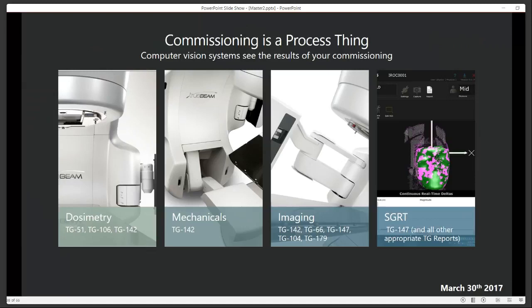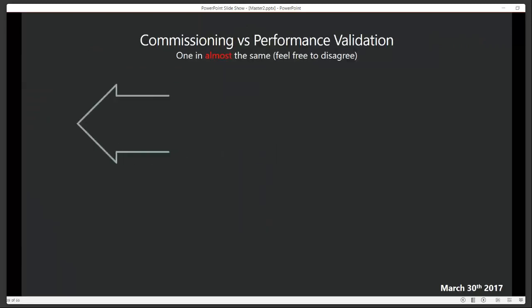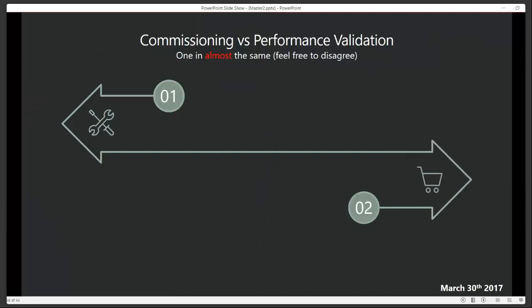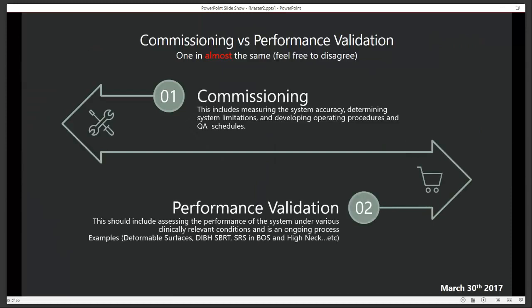And so you really need to make sure that your commissioning is a very tight process and that it's very well QA'd, because the SGRT system is seeing the scene of your treatment. It does not distinguish between a couch walkout and a patient motion. You need to do that as the physicist. And so having a very tight commissioning is very important with an SGRT system. It's not a standalone, if I commission this, it corrects for all of the wrongs of the other commissioning. So as I said, commissioning and performance validation are one in almost the same thing.